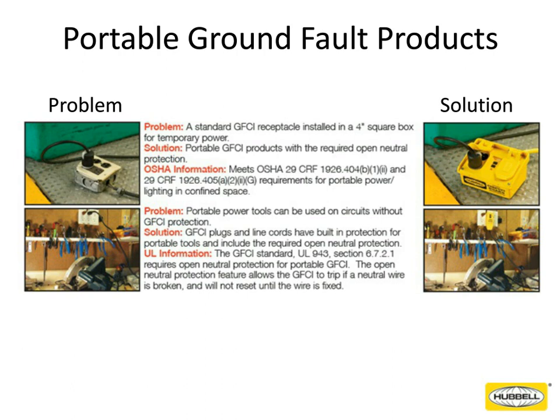So portable ground faults must have the added safety of having an open neutral relay. If that cord that's feeding the equipment has the neutral cut, the GFI must trip. So it trips under a ground fault, and it trips under a neutral being cut. And that's why, in the picture on the left, the problem is somebody's made a homemade ground fault, which is not acceptable. You must use an OSHA-approved unit that has open neutral relay.